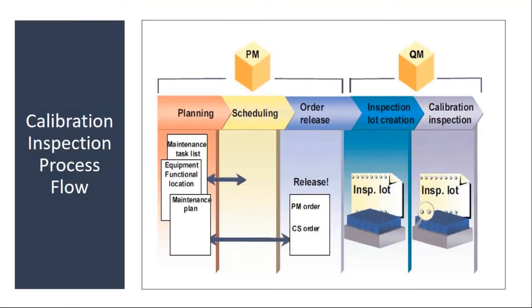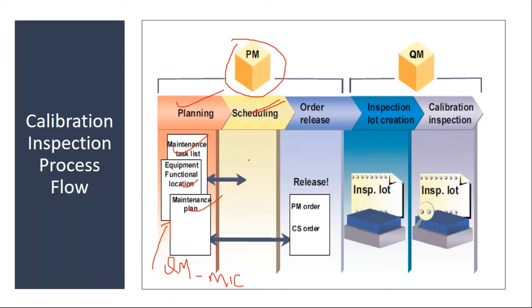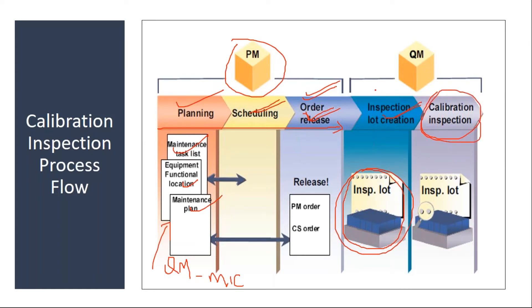The process flow starts with planning activity in the PM module. They will create all the necessary master data, and in this master data you will link your QM MICs. After that they will do the scheduling, and when scheduling is done it will generate an order — normally called a calibration order. When the calibration order is created and released, the system will automatically generate an inspection lot, and using this inspection lot they will do the calibration activity in the QM module.